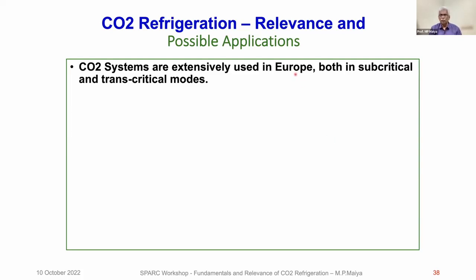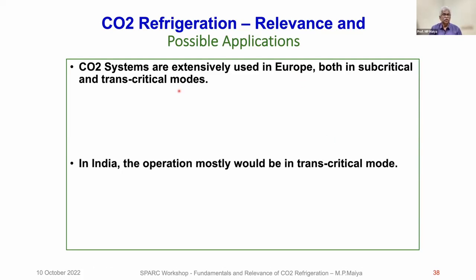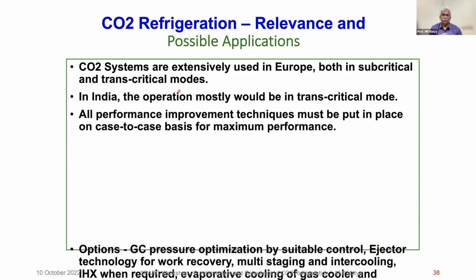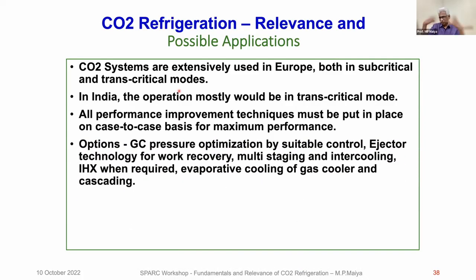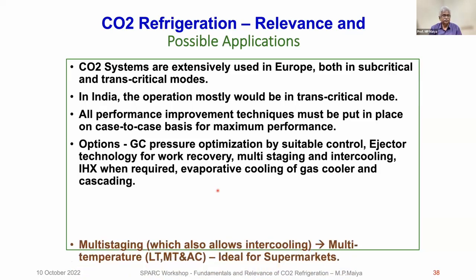Okay, so possible applications. CO2 system is extensively used in Europe, both in subcritical and transcritical modes. In India, the operation is mostly transcritical mode because of high temperature. All performance improvement techniques must be put in place on a case-to-case basis for maximum performance. Options: gas cooler pressure optimization, ejector technology, multi-staging, intercooling, IHX when required, evaporative cooling of gas cooler, cascading. Whatever is explained, it may not be possible to use all, only whatever is possible.